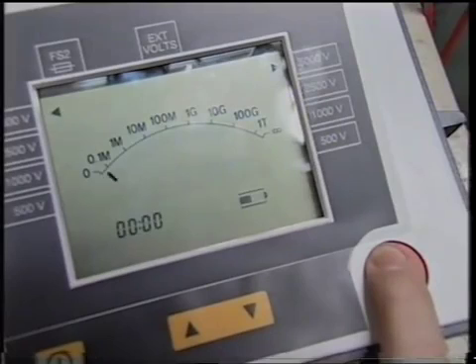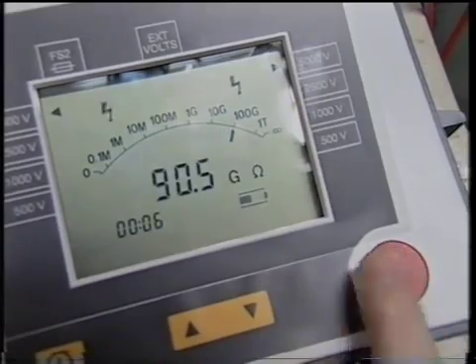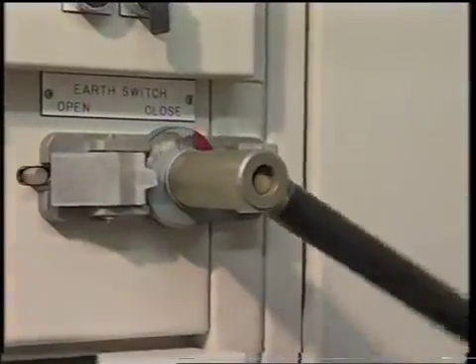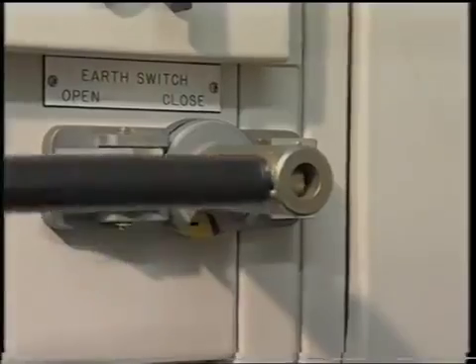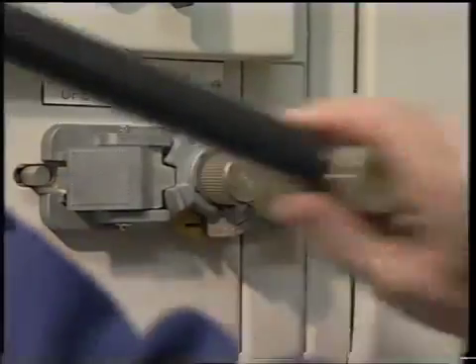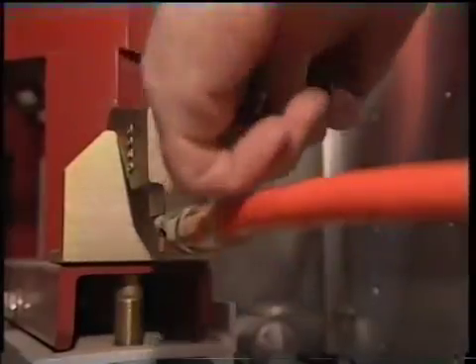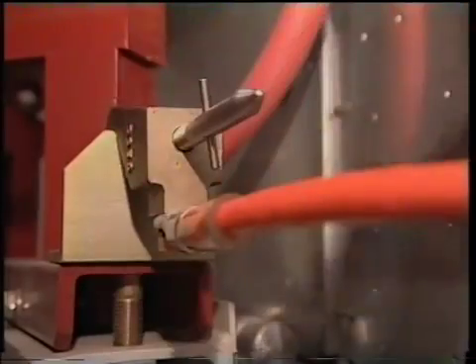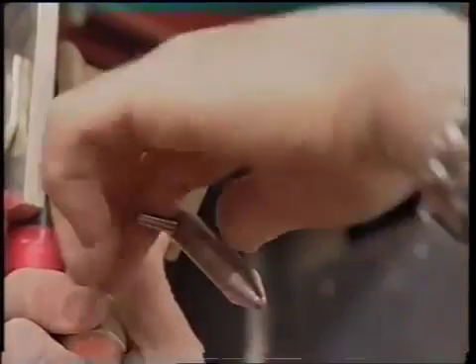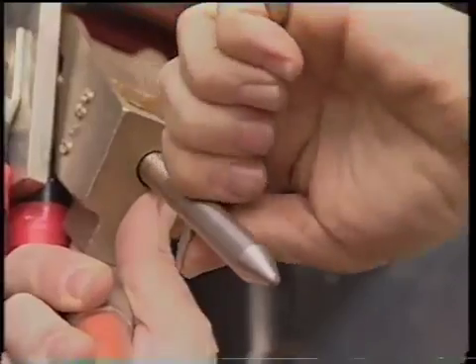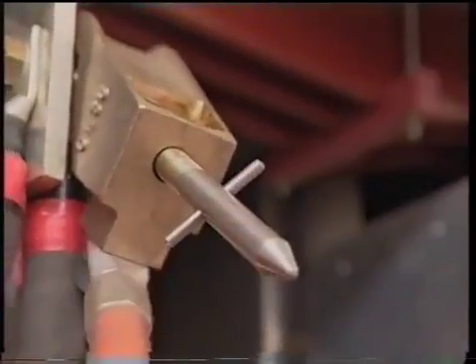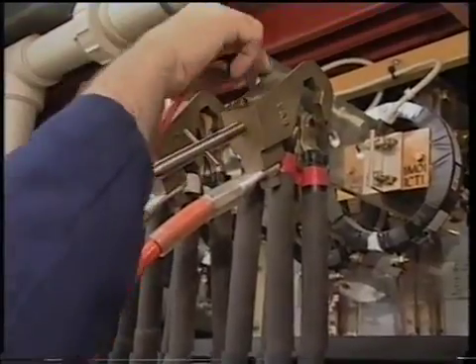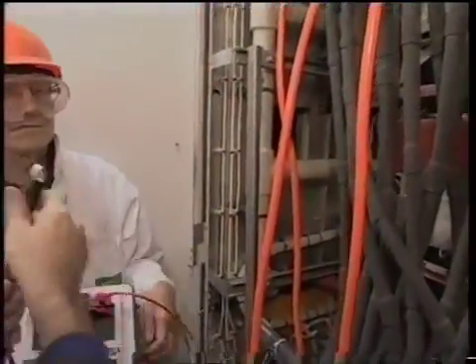And now the insulation tester measures between the phase and earth and shows a healthy IR value. The circuit breaker earth is reapplied. The additional earth is reconnected to the 3 phases for operator safety, and the IR tester is disconnected. This process will be repeated to apply the IR test from the other 2 phases to earth, and then between each pair of phases.